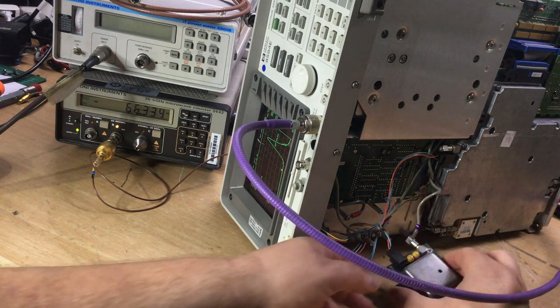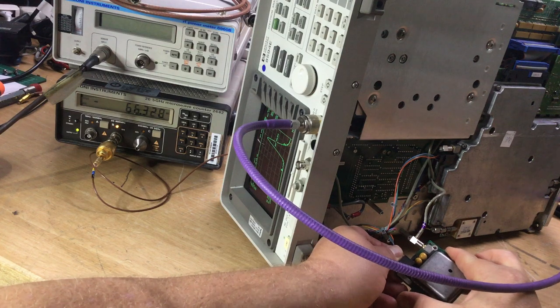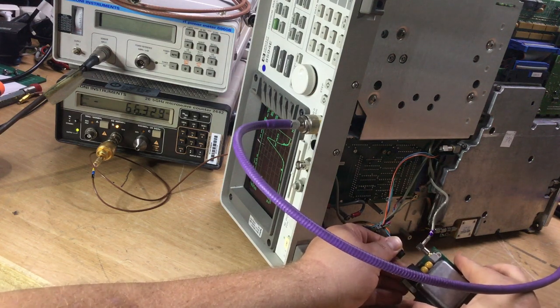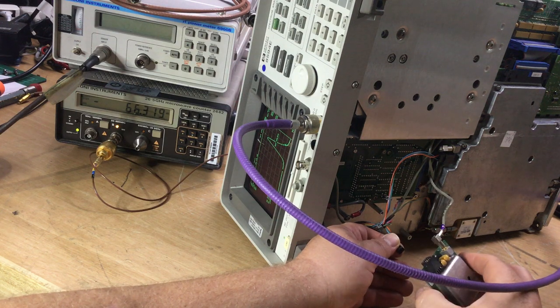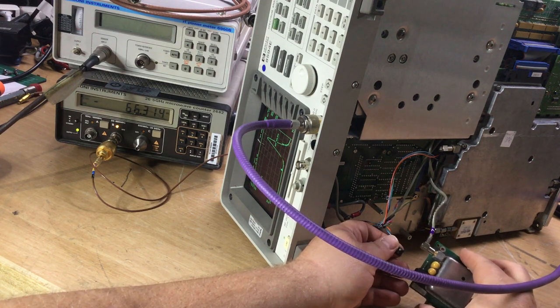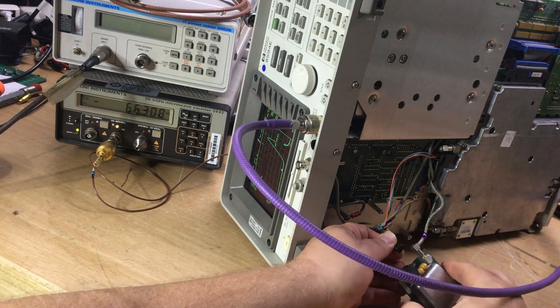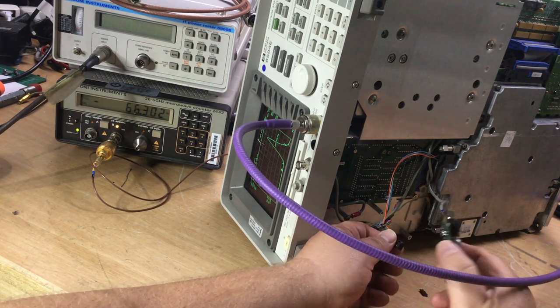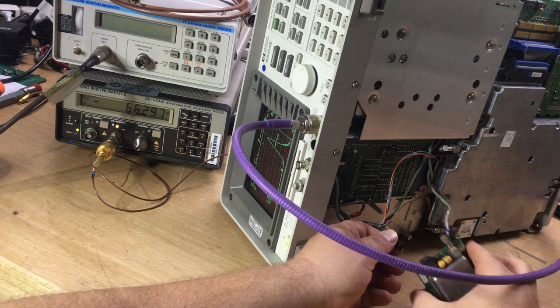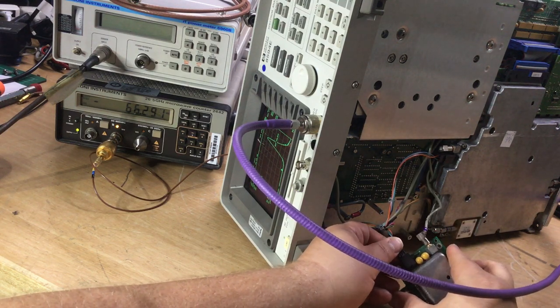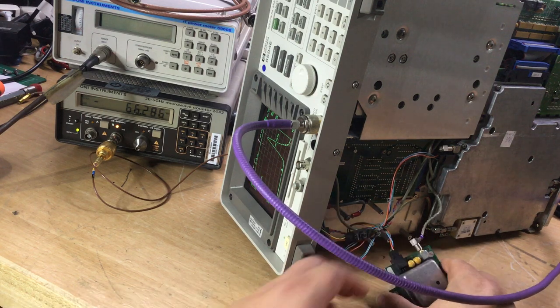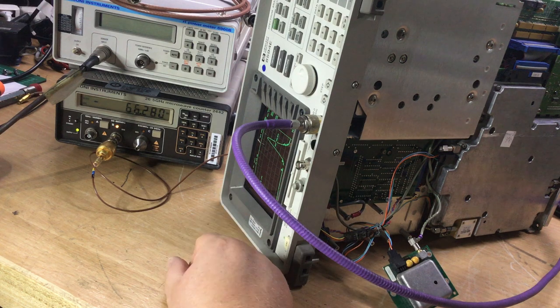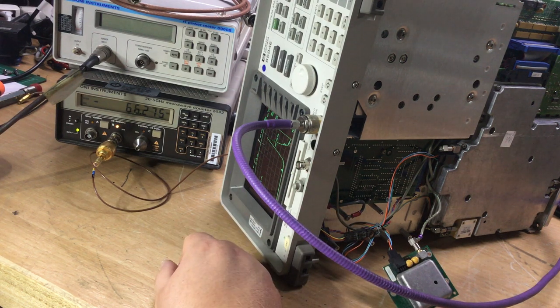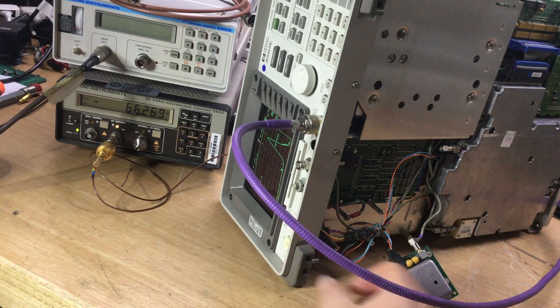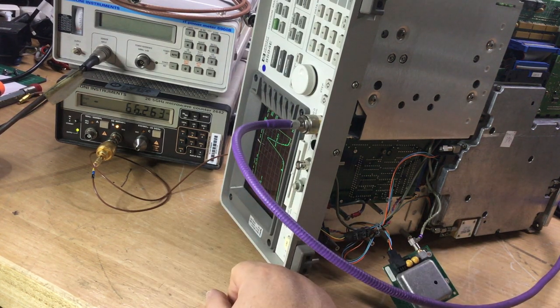Just disconnect the power to it. See whether it... So even with the signal removed, I think once it's gone into lock, then it will remain in lock. We'll have to power cycle the instrument, because I've removed the power to the 10 meg reference oscillator board. So naturally that signal should be needed to allow the phase lock loop of the 600 megahertz signal to operate, and naturally if that's not present, that signal shouldn't be there anyway, it should have vanished. So there's something strange going on here.